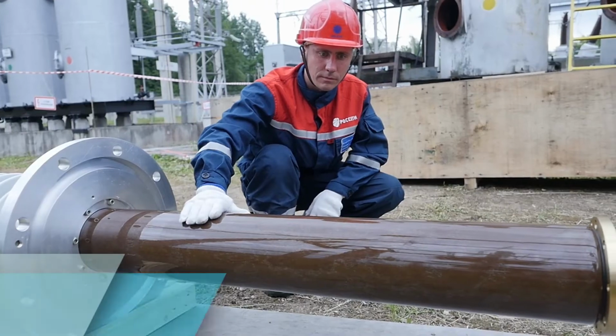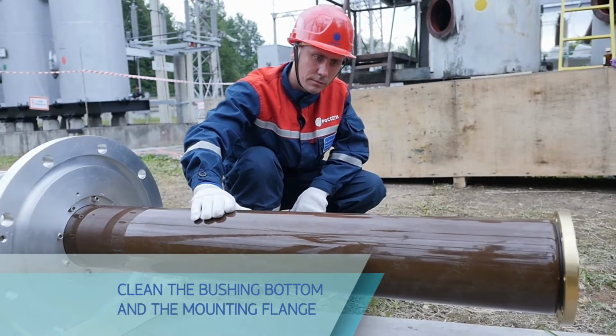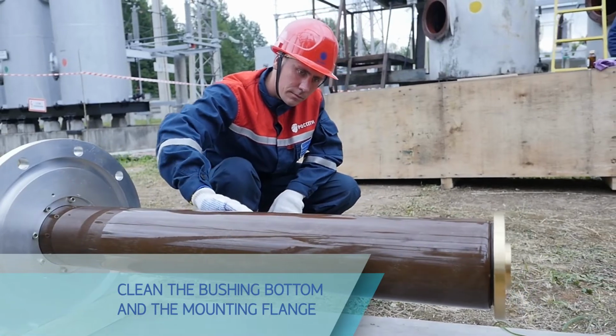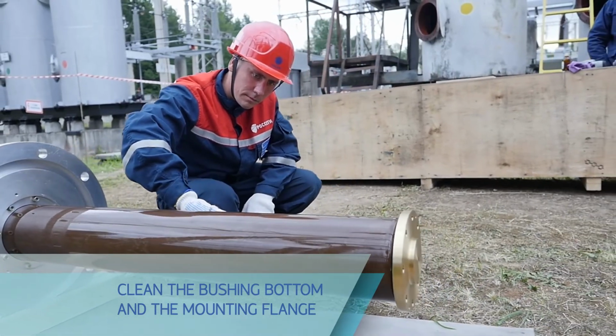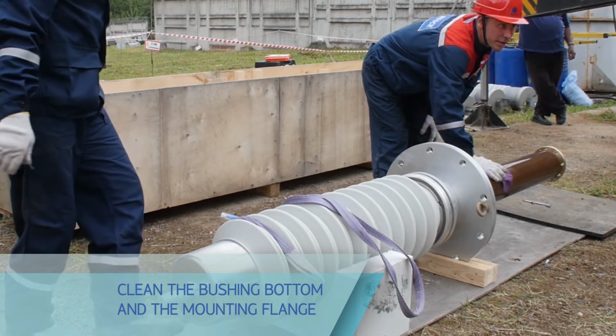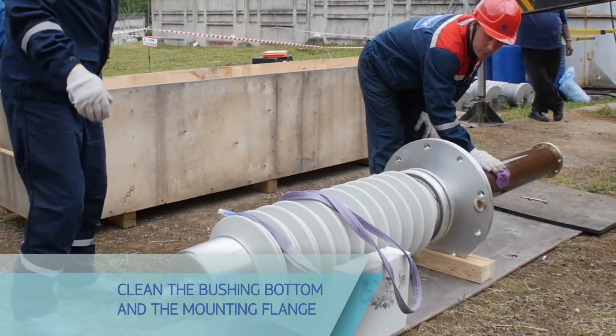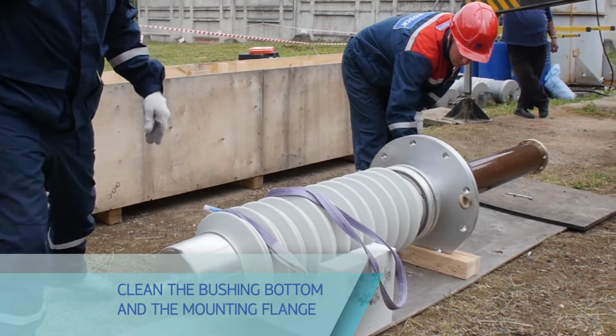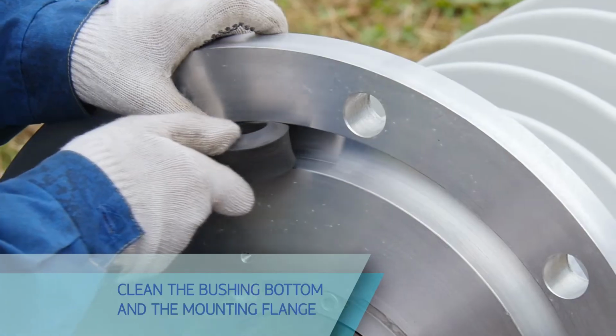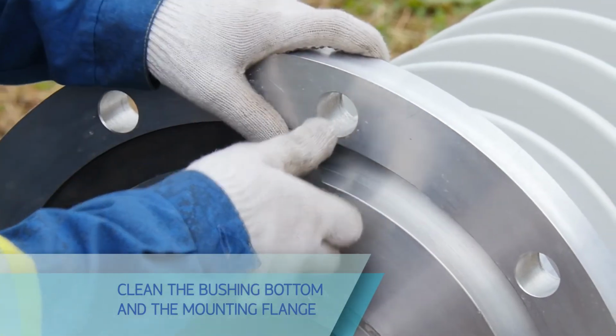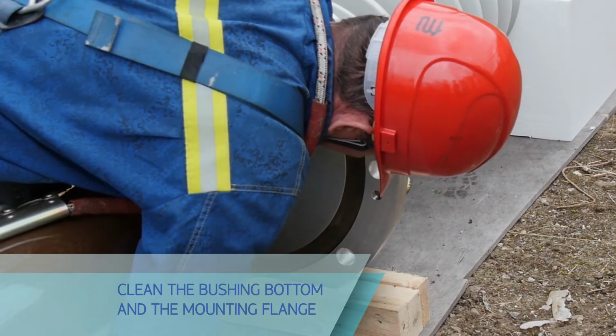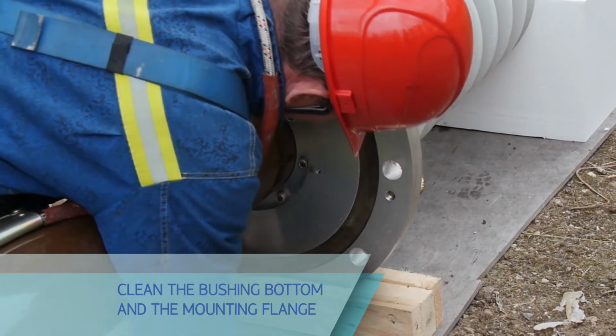Wipe the bushing bottom and the mounting flange using a cloth wetted in an anhydrous solvent. This procedure shall be done before measuring properties of internal insulation of the bushing in order to obtain accurate results. Before setting the bushing to a vertical position, insert a rubber gasket into a mounting flange groove. Thus, we have examined the bushing exterior.